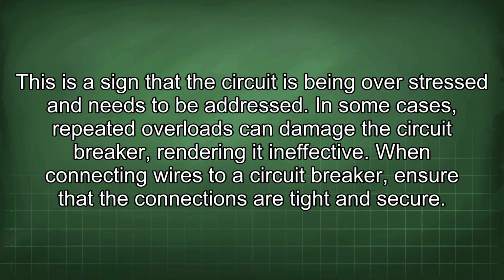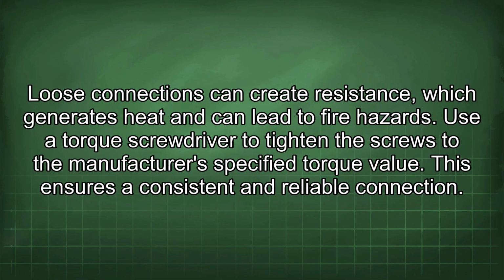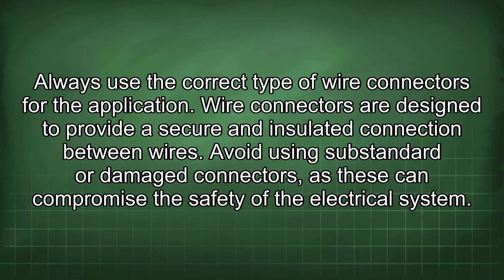When connecting wires to a circuit breaker, ensure that the connections are tight and secure. Loose connections can create resistance, which generates heat and can lead to fire hazards. Use a torque screwdriver to tighten the screws to the manufacturer's specified torque value. This ensures a consistent and reliable connection. Always use the correct type of wire connectors for the application. Wire connectors are designed to provide a secure and insulated connection between wires. Avoid using substandard or damaged connectors, as these can compromise the safety of the electrical system.